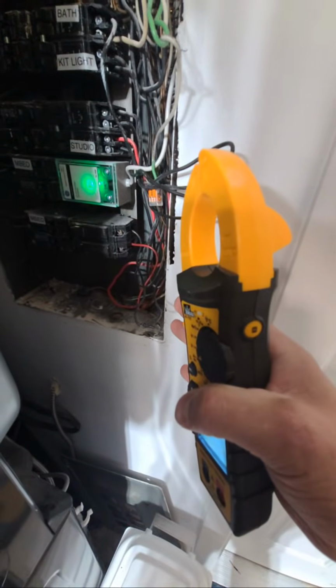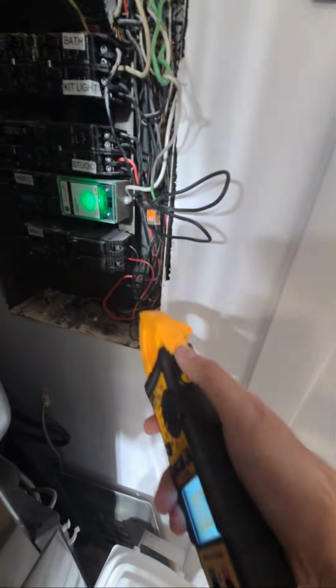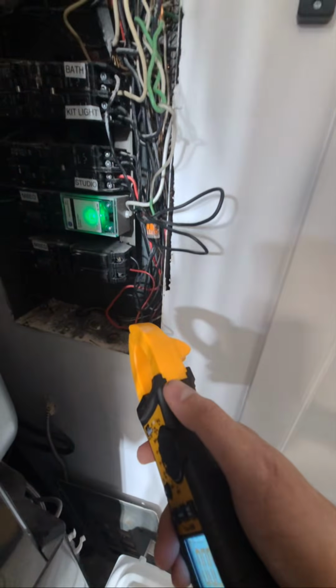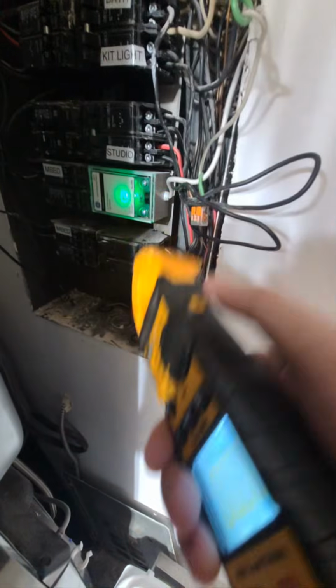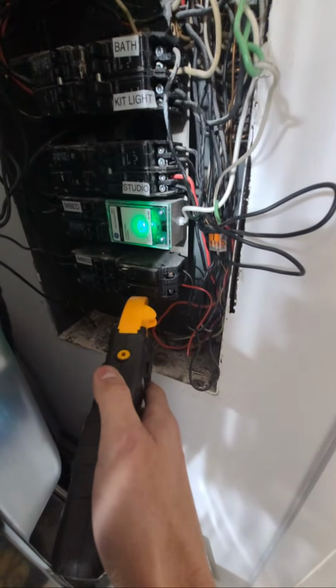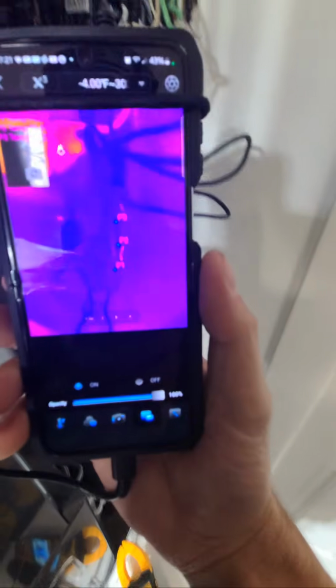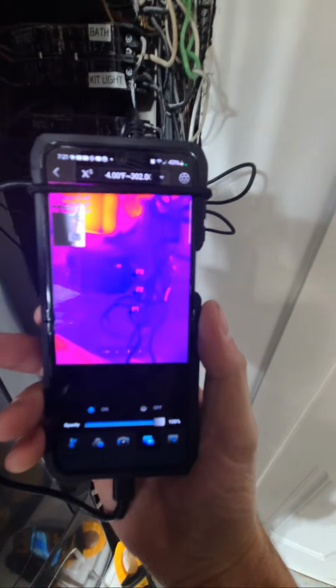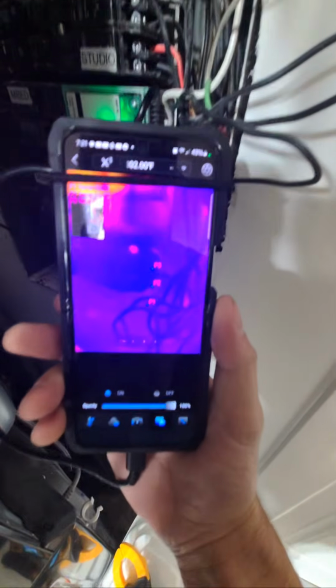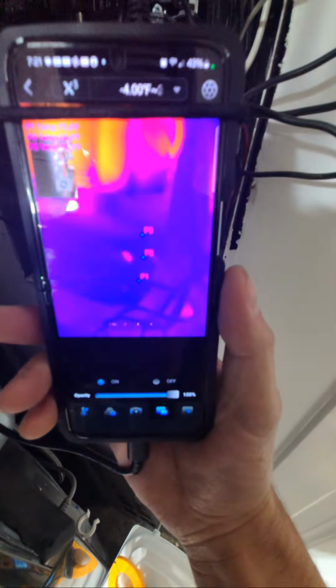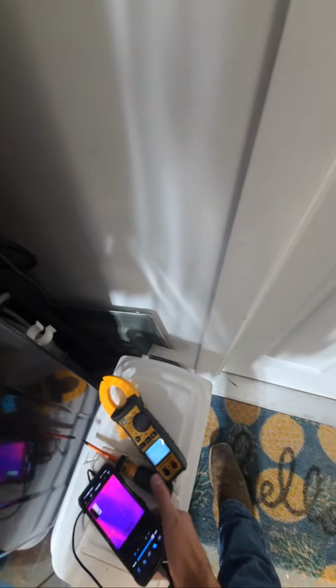and if everything was tight and there wasn't a problem, we should not have a difference in temperature on these wires. If we were comparing 2 different breakers, and one was pulling 14 amps and one was pulling 3 amps, well then yeah, looking at your infrared camera, you could say, I don't think that's a problem. You can see we're just tightening that, just that little amount. Got it less hot that fast. We're going to loosen it again.